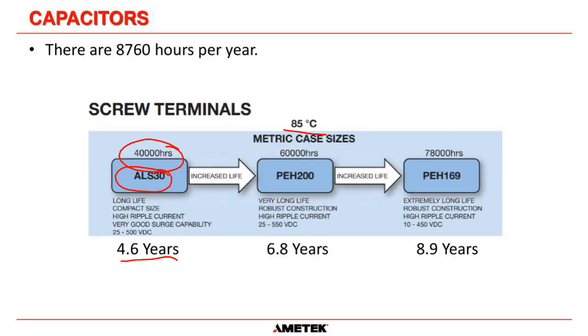And that is not the case for our capacitors. This one here is 60,000 hours. That works out at 6.8 years. And this one here is 78,000 hours, and that's 8.9 years. Now, remember, I just took this from a random capacitor manufacturer data sheet, and that's for an 85-degree temperature. So that's where we get our time from.